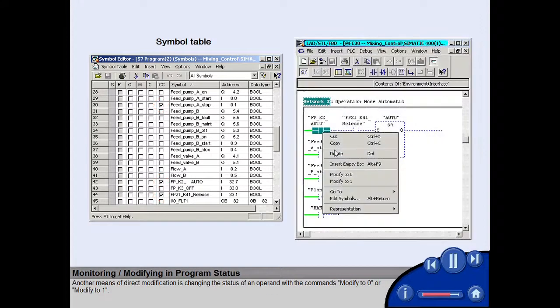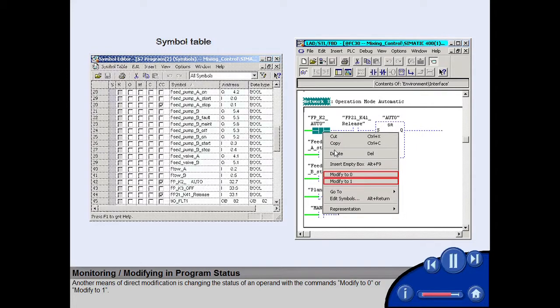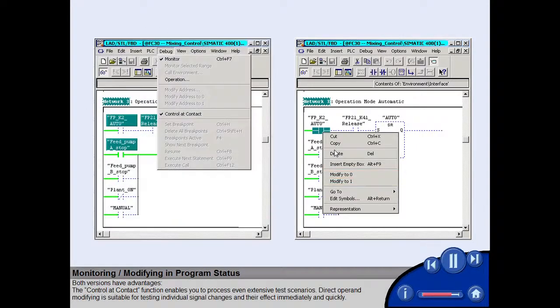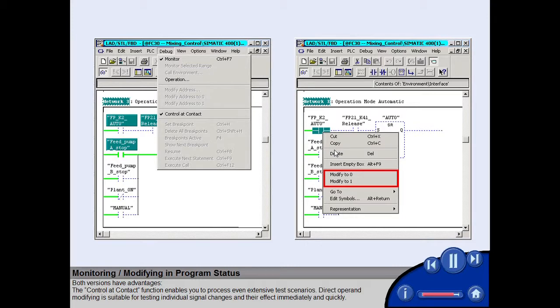Another means of direct modification is changing the status of an operand with the commands Modify to 0 or Modify to 1. Both versions have advantages. The Control at Contact function enables you to process even extensive test scenarios. Direct operand modifying is suitable for testing individual signal changes and their effect immediately and quickly.